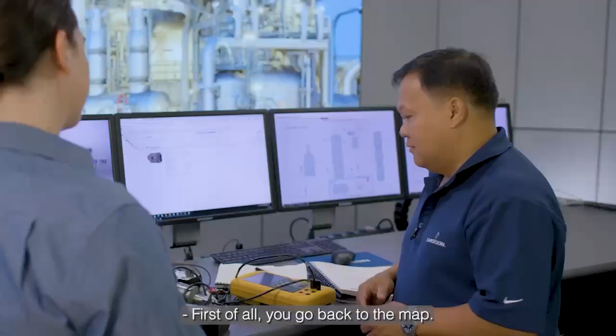First of all, you go back to the map to figure out where the device is at, and make sure the device is within scheduled maintenance for calibration. Typically within a day you'd schedule 2 to 5 devices for calibration management. Once you have your route list, you bring your loop calibrator with you for documentation, and it provides information on the accuracy of your instrumentation.